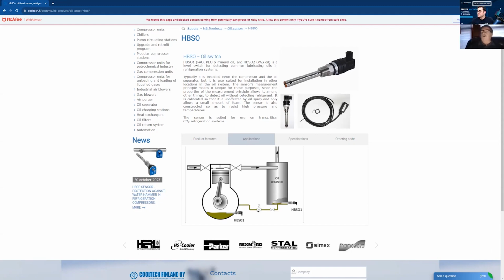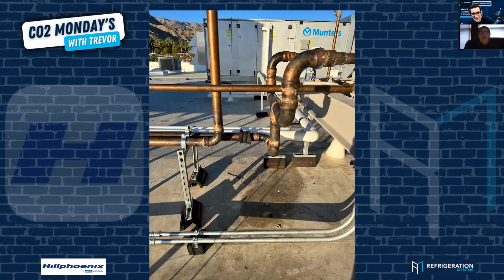Pull the head off. Just don't order a new switch. Pull the head off. It could be the wires were loose and have now come loose. So important, just little tips like this. Test it first. Then our cube relay makes an input to the input screen, and on an Emerson that'll be a flex combiner. Look at the flex combiner. It'll say high oil separator will be on and tell the system to work. So follow it through the whole cycle. Don't just say, hey, I'm not feeding oil, let's replace the HBSO2 sensor three times before we call somebody.